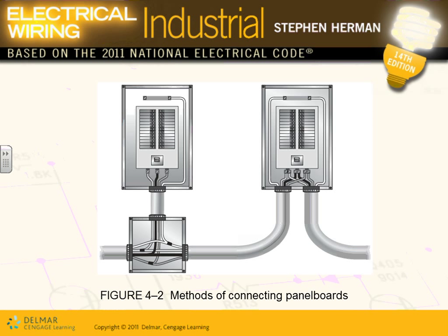So that's a sub-feed. Actually, with the sub-feed, the feeder could be more than the panel. So I can have a 400 amp feeder here feeding 200 amp plus 200 amp. Any questions, guys, about the subfeed?